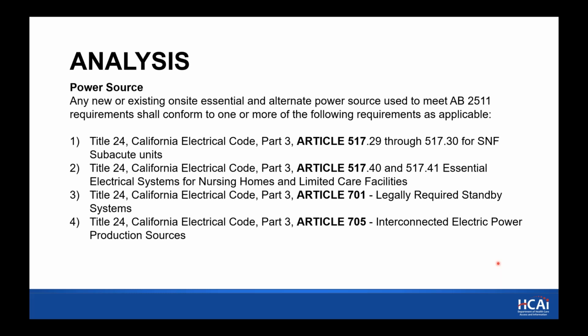Yes. So in order to help understand how we'd evaluate projects that are being submitted, I've identified that the law doesn't require emergency power for these new loads. It requires an alternate power source. So I've identified that you could either take the tack of adding this to your existing 517 essential electrical system, you could take the path of adding this to a separate legally required standby system, or you could take the approach of introducing an interconnected electric power source, which would follow Article 705, better known as healthcare microgrids. As we go on, I'll talk more about these.